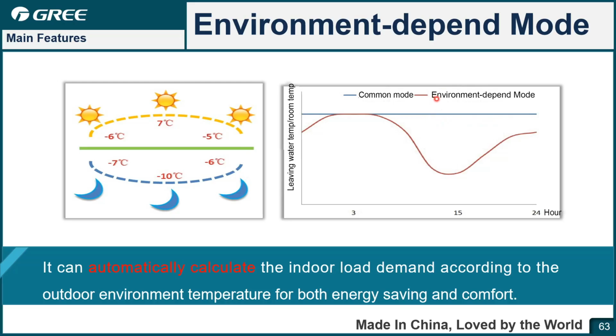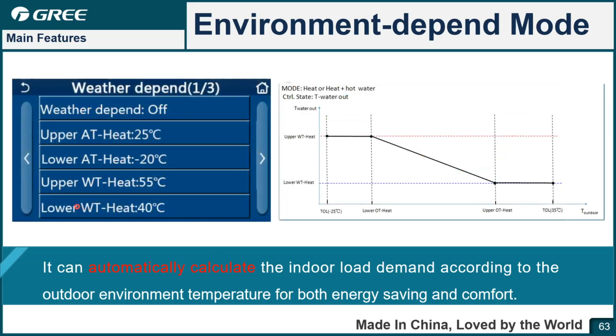However, if you set the environment dependent mode, during the daytime or nighttime, because of the ambient change, the water temperature will also change. In the daytime and nighttime, it can adjust the water temperature to satisfy the demand of the customer, and also reduce the power consumption. It can automatically calculate the cooling or heating demand according to the outside ambient and balance energy saving and comfort. Here is the setting page in the controller.